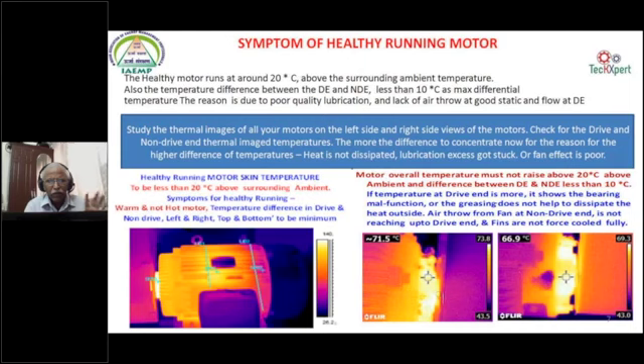With an ambient temperature, our Indian ambient, let us say around 40 degrees in the industry, if the motor is running around 60 degrees at the skin, measured by the thermal imager, it is excellent. If the measured temperature is more than 70 or 80 degrees, the motor is going into overload. Why is it going into overload? Let us look into it. And if the motor temperature is almost near 40 degrees, or only 5 or 10 degrees more, the motor is idling.